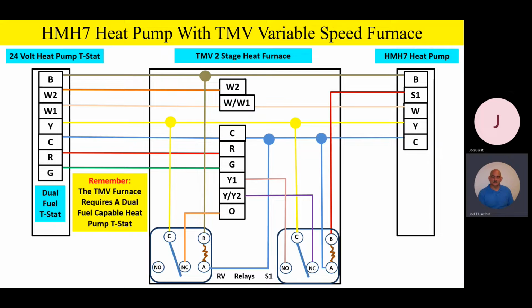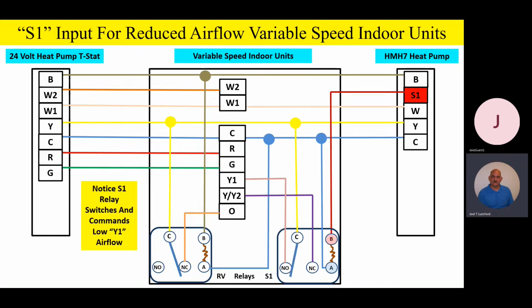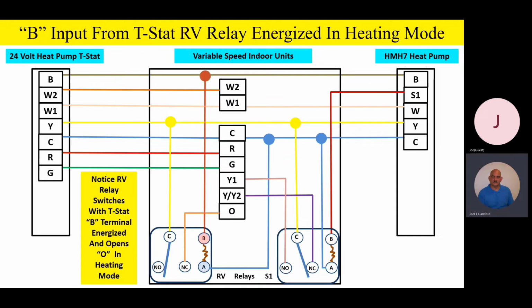Okay, so let's go ahead and, just a quick reminder, the TMV furnace does require a dual fuel heat pump thermostat. And then let's look at some animations. We notice that when we switch S1 from the outdoor unit, just like we had before, we're going to switch the S1 relay for low airflow. And so that S1 relay switches and commands low Y1 airflow on the indoor unit, just like we had before. Now watch closely on the animation. We notice that the RV relay switches with the thermostat B terminal energized, and it opens that O terminal in the heating mode of operation.